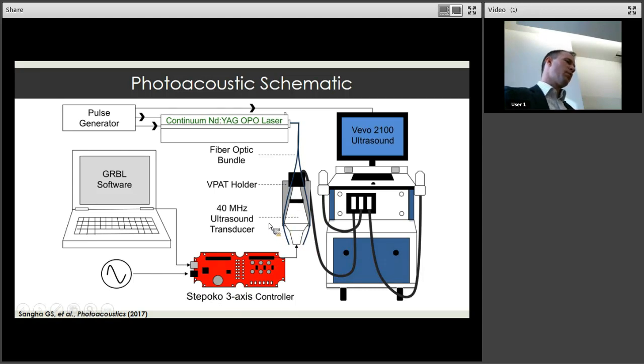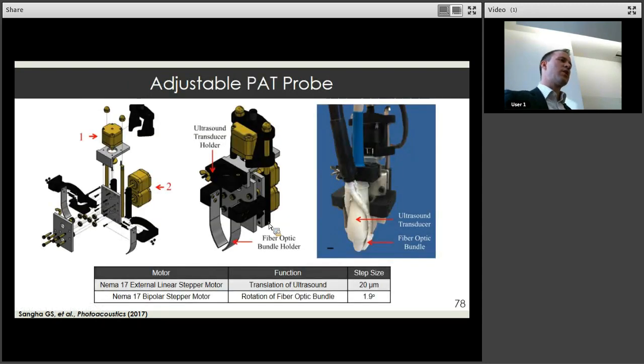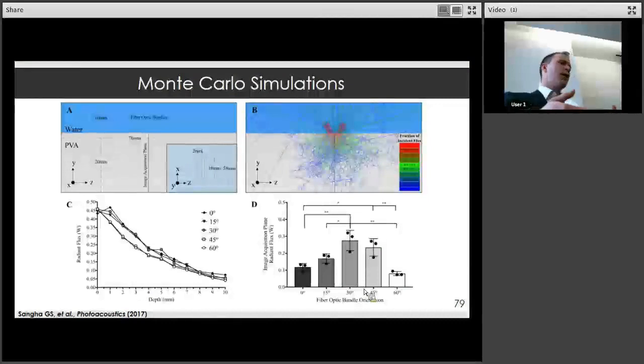So that's what the photoacoustic paper was about, where it started as a senior design project with a couple of undergraduate students that led to a lot of really interesting work developing a better way to combine the fiber optic probe with the ultrasound transducer in a controlled way. Instead of just taping it together and hoping you have about the right area, now this is very controlled, allows us to identify exactly where we want the light delivered and optimize between shallow and deep imaging depending on our applications. We did some Monte Carlo simulations, which allowed us to look at, with ray tracing, where the light is delivered. Sure enough, you get this nice bell-shaped curve depending on the fiber bundle orientation and the image plane and how much is being delivered.